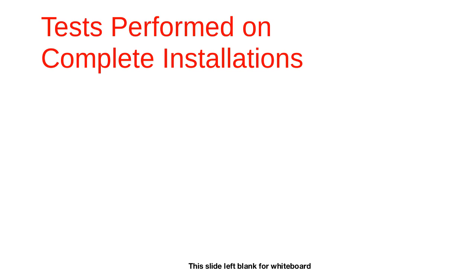The next thing that you check is the building's sealing around cables and the trunking. So you check the trunking, how safe are they? Have they been done well? And also the sealing of the building. Next is the presence of means of earthing. You check if your installation has been earthed correctly.